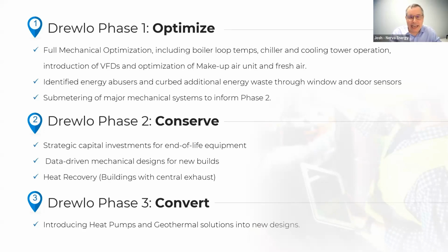Next, it's about identifying energy abusers. And let me state a fact that we've come to find out through the implementation of this type of methodology through hundreds of multi-res buildings. Oftentimes, we find that 5 to 10% of the residents in a multi-res building can be up to 40% of the annual HVAC load, and hence the annual HVAC energy usage. We call these people the abusers, and they're typically wasting energy through either having set points on their thermostats way too high or way too low, depending on the season, and leaving their windows open for extended periods of time while their heating and cooling is operating.